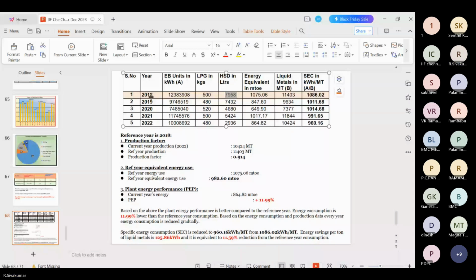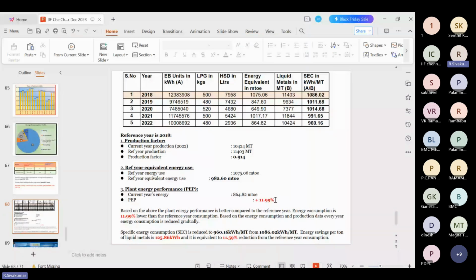2018. So based on the data collection, because the unit gave us the data, we are analyzing the best part also. By keeping on implementing energy conservation measures, the Foundry unit's specific energy consumption is reflected, so that the unit can save nearly 12% of the overall energy compared with the year 2018. They achieved 12%, and the specific energy consumption is reduced to 960 units from 1086. The energy savings per ton is 125.86 units per ton, equivalent to 11.59% from the reference year consumption.